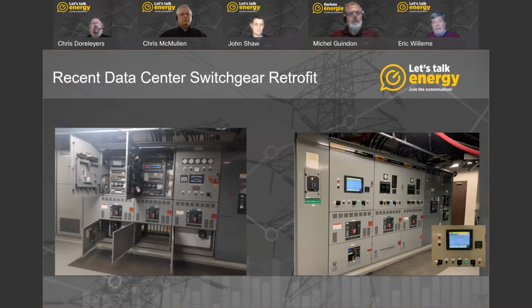The audit identified the fact that in addition to the generator controllers, several synchronizing and protective relay components were obsolete. This system was installed in the year 2000 and all of the control hardware was 21 years old. If you look at the photo on the left, the first open door contains the PLC and the HMI. The PLC rack can be seen on the top of the backplane. This PLC was of an age that the OEM no longer has spare parts.